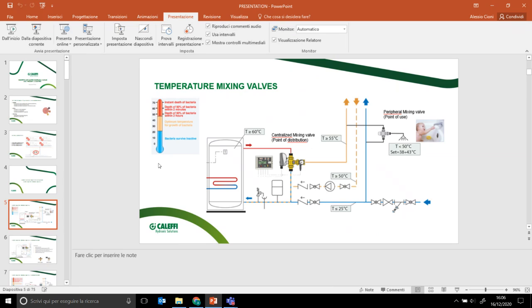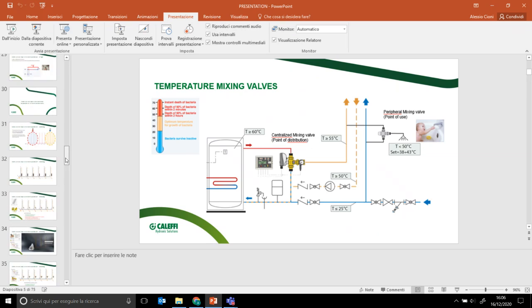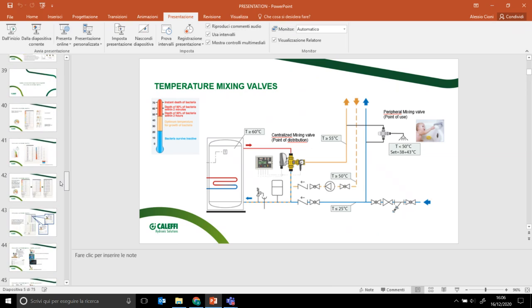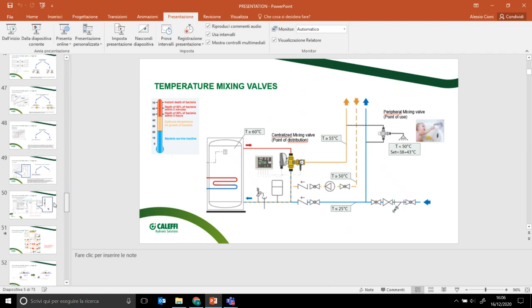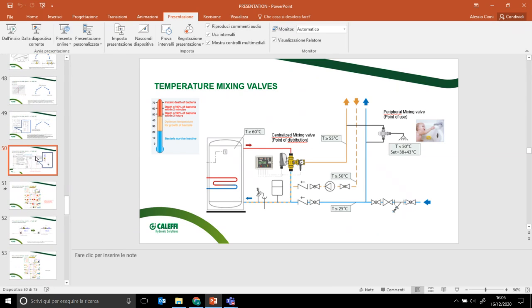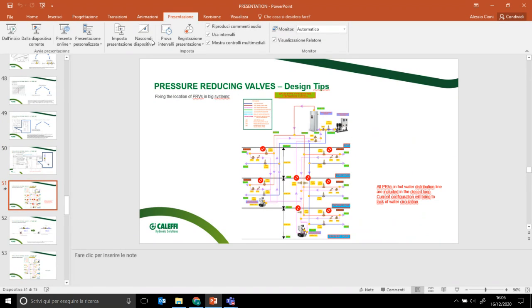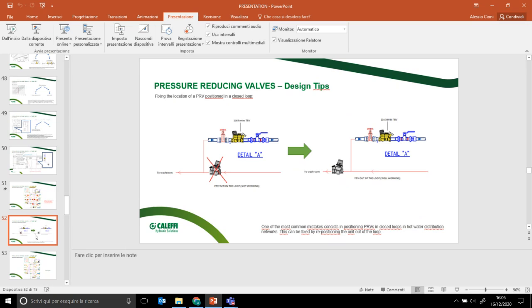Okay, next one. Can you put PRV in the hot water return? I think the short answer is no. The short answer is no, for what maybe I too briefly explained before. So the problem, okay, this diagram can be good. The PRV is a mechanical device. So how does it work? As soon as you get downstream the pressure value that you preset, the valve will close the flow rate.